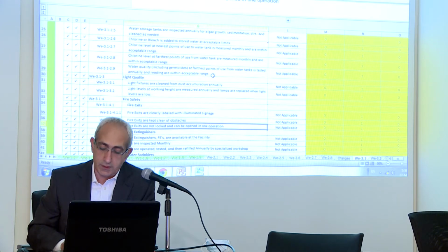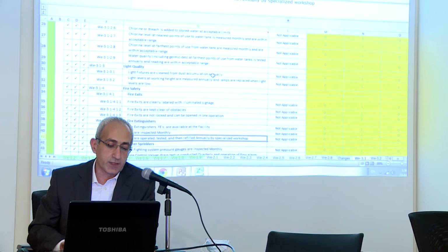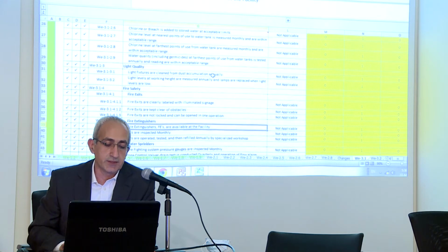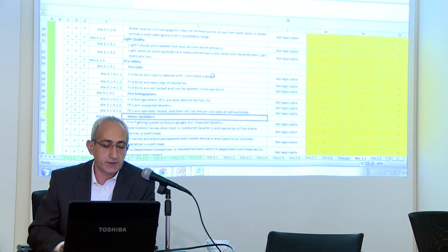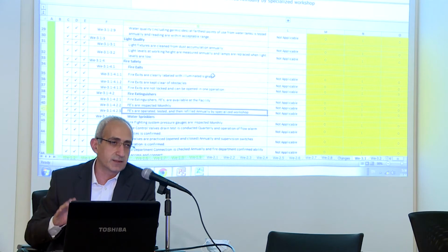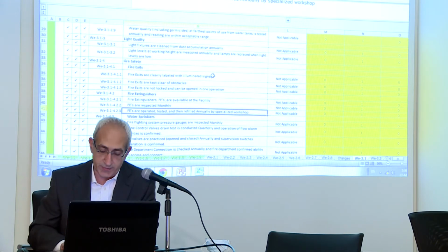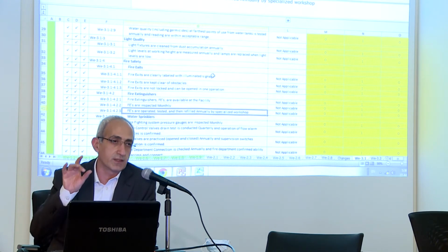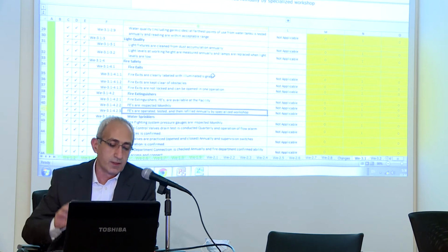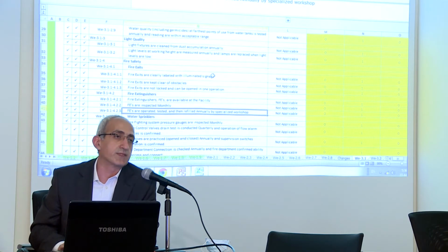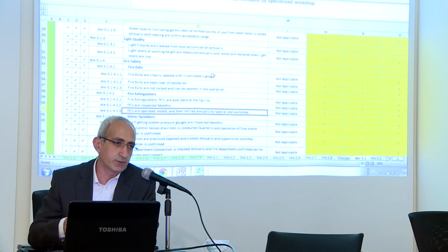We also look at fire extinguishers. So fire extinguishers are available at the facility. They are inspected monthly, by visual inspection, and they are tested annually, operated and refilled. The standard is usually to just inspect them and fill them whenever the gauge is at zero. The actual requirement is to empty the extinguisher and then fill it again to test the mechanism on an annual basis.